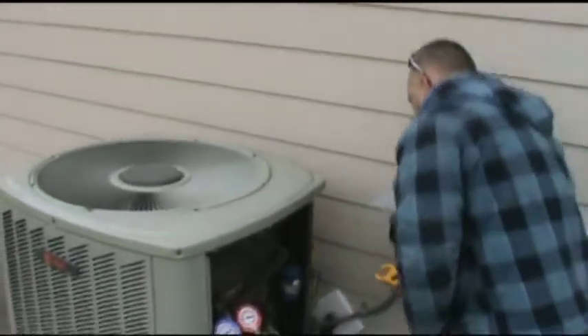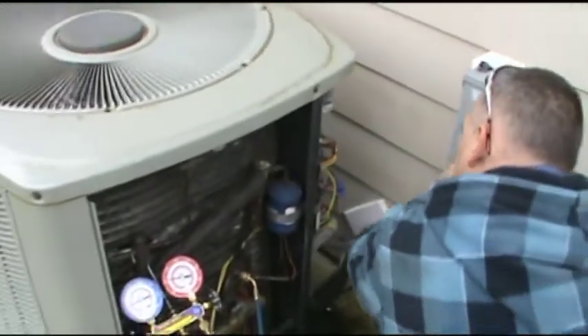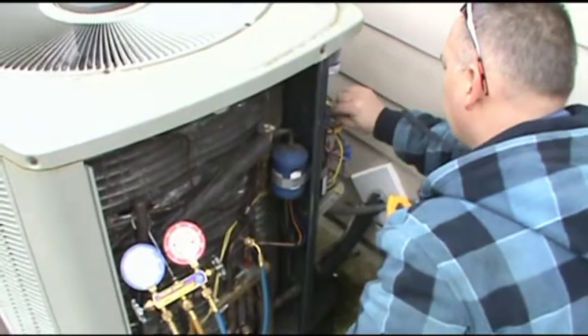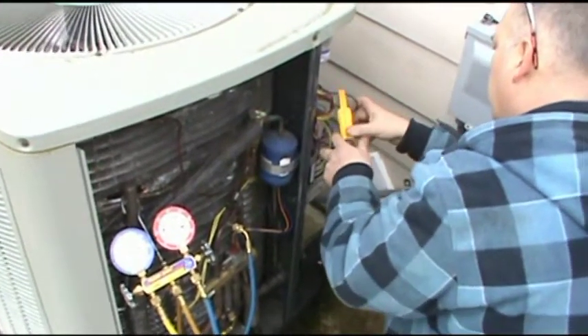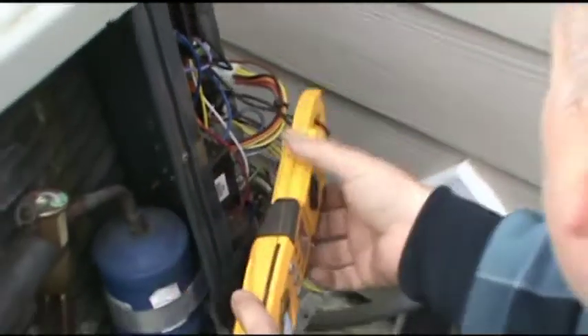Again, we're going to check the amp draws on our compressor and our condenser fan motor out here. Make sure those are within specifications. So we have an amp draw of 1.3 on the condenser fan motor. And if we reference the nameplate on this unit, it's 1.4. So again, we're very close to what the system is rated for.